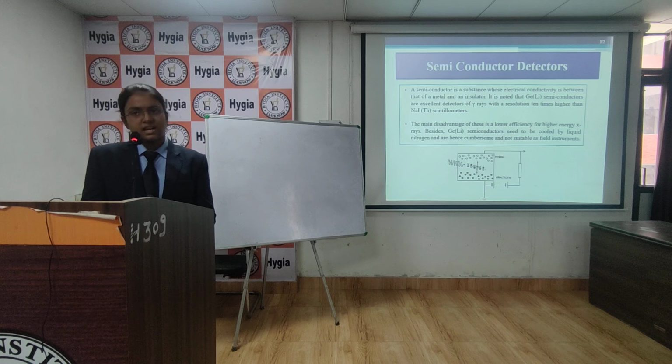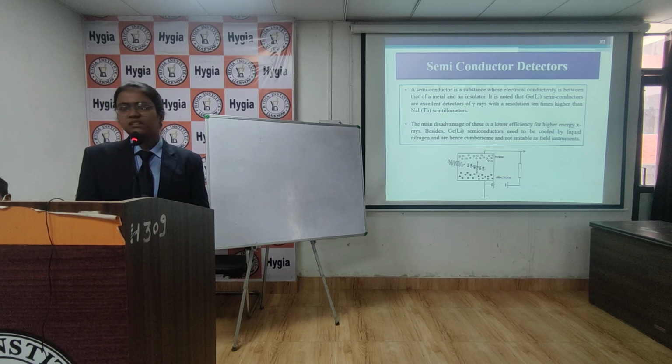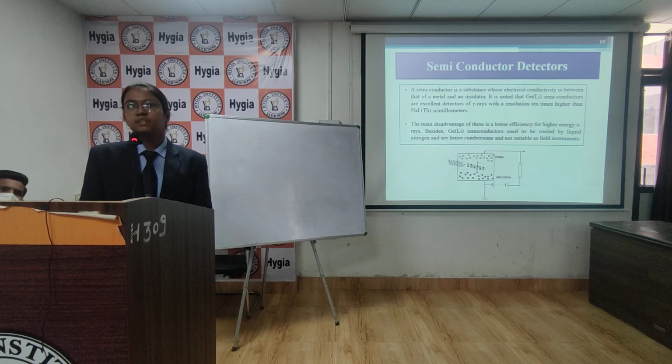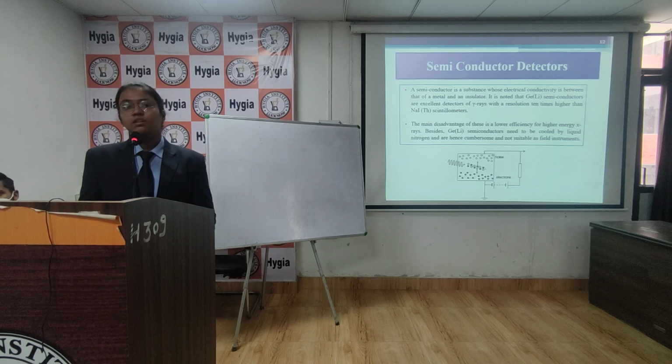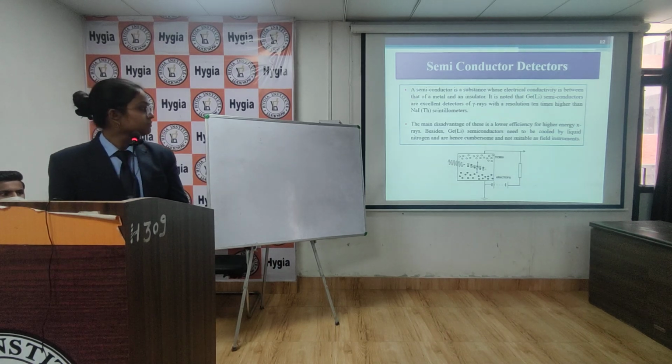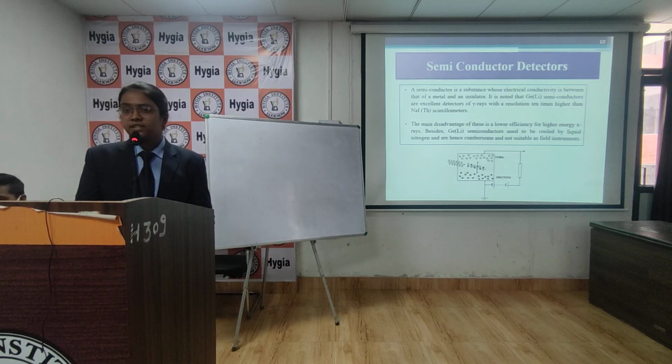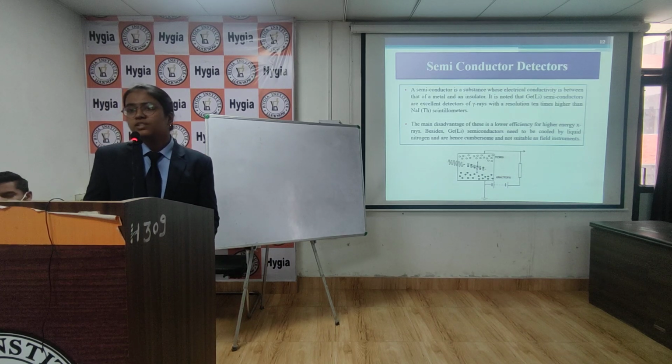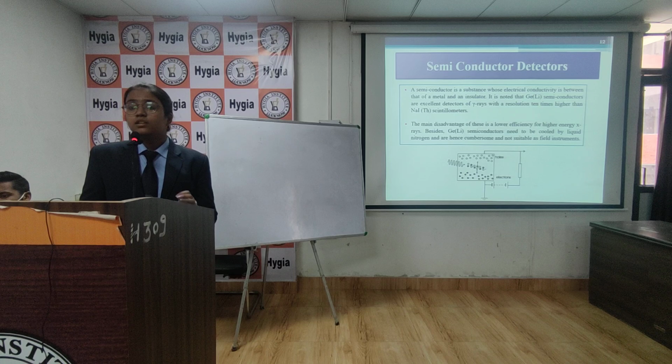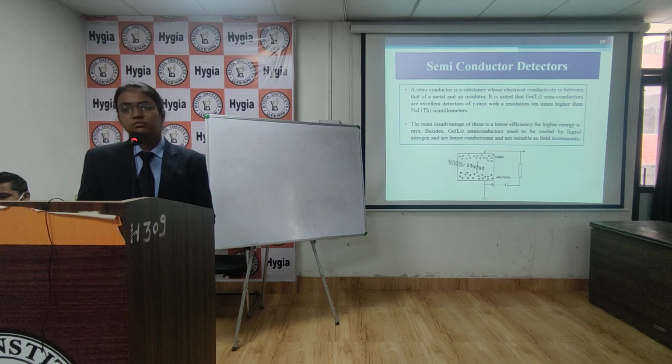The main disadvantage of using these is that it is very cumbersome, because germanium lithium detectors need to be cooled with liquid nitrogen. And the other disadvantage is they can only be used for measuring lower efficiency, lower value gamma and X-rays.